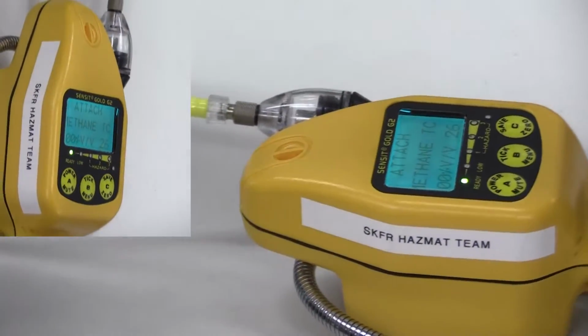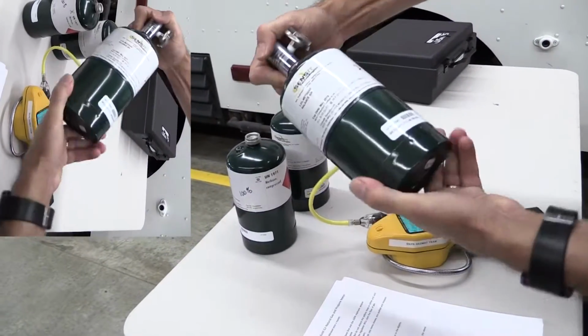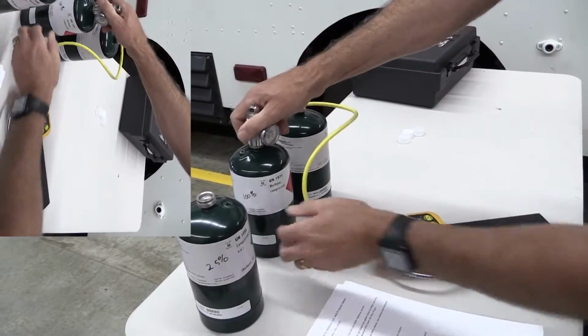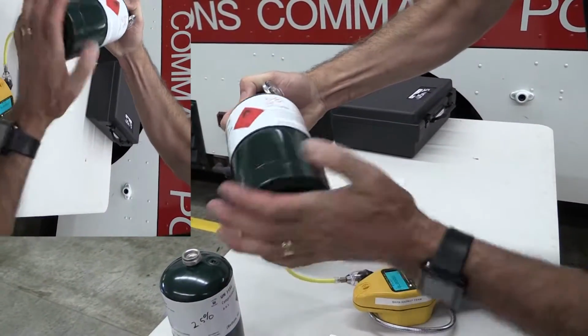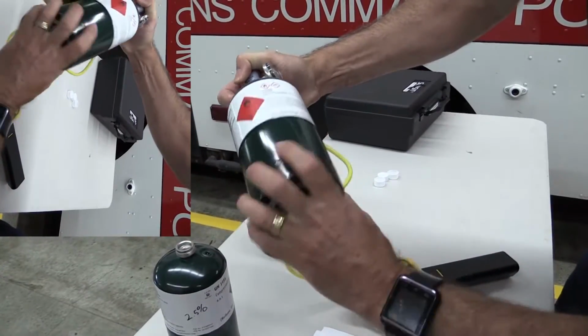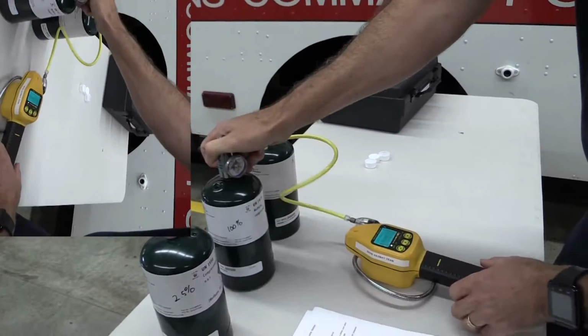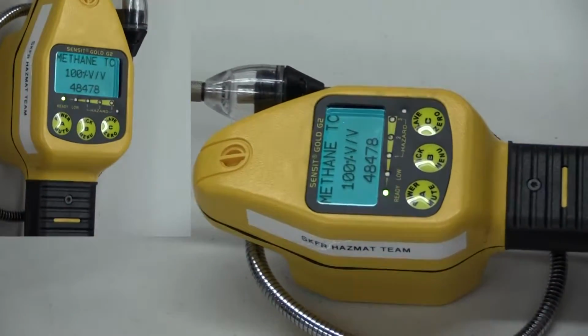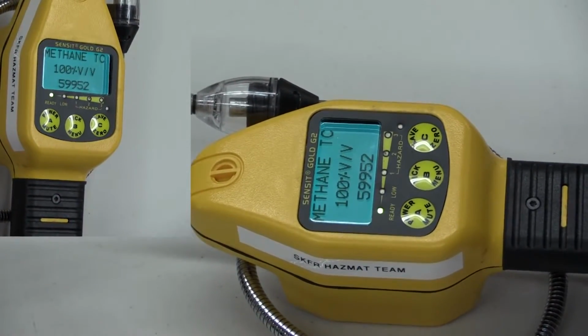Now it's telling you to attach the 100% methane. Again, you have 30 seconds to do this. You can just take the regulator off of the bottle and put it on the other bottle. You may get a flow blocked message while you do this. Don't worry about it. Once it starts reading the methane, it'll continue to set it up.